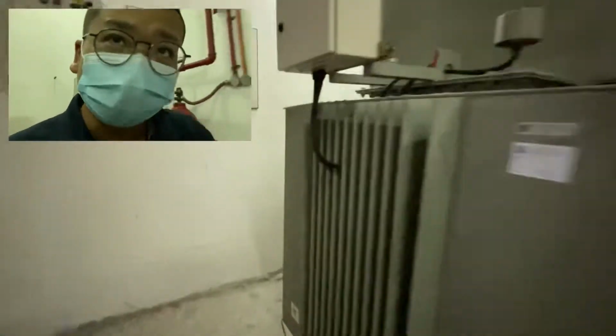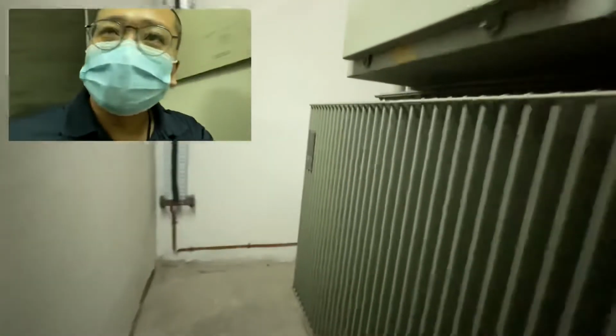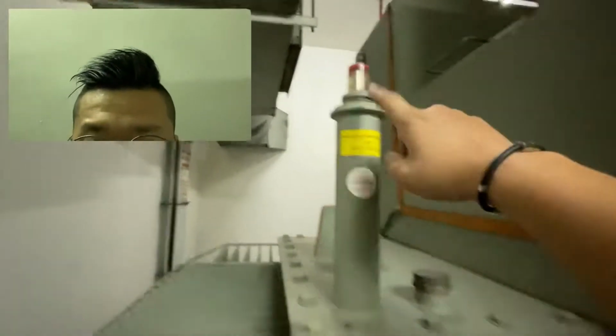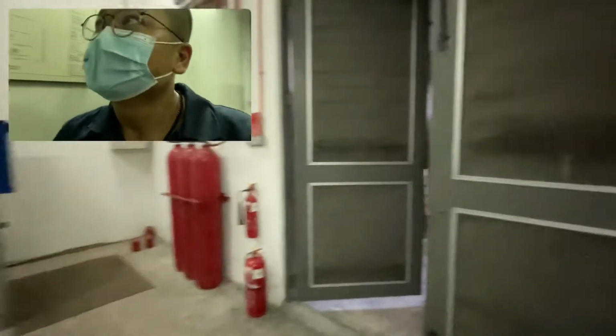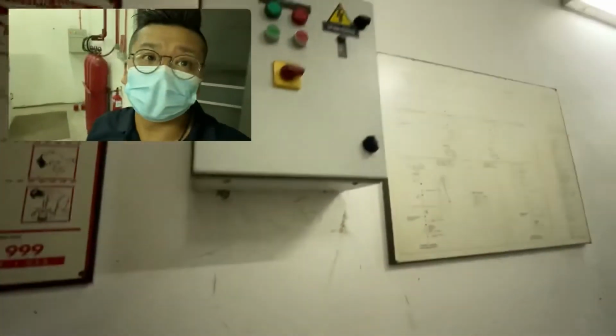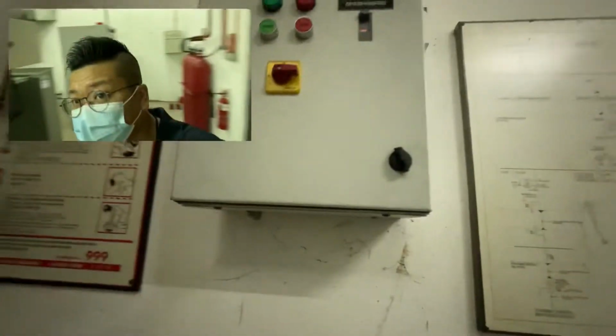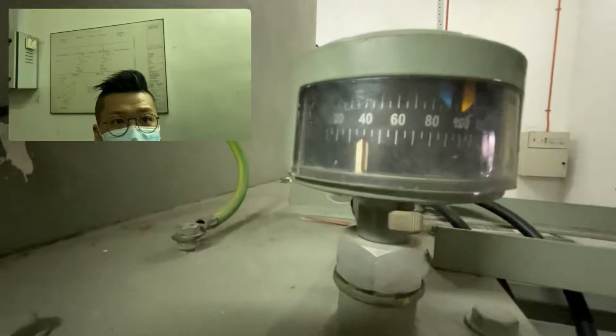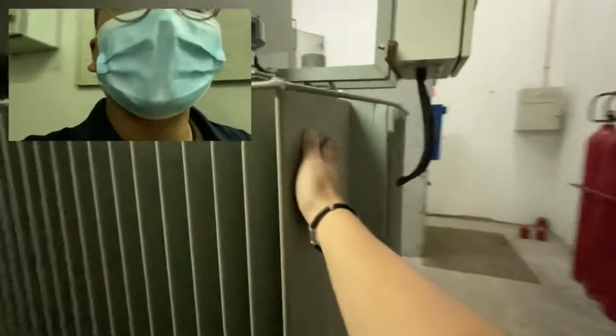So this is the Onan transformer. Oil natural, air natural. It's a SGB brand. Oil level okay. The room exhaust fan is not running because it's based on thermostat. Currently the thermostat is set at 35 degrees Celsius. Let's check the temperature of the transformer. About 40. Let's feel and see.